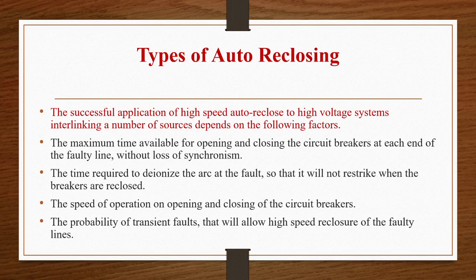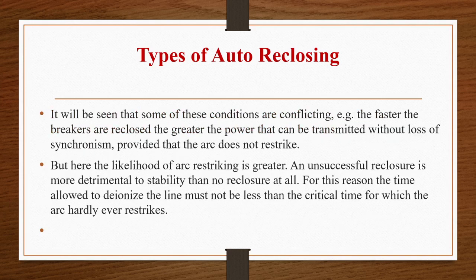Second one is the time required to deionize the arc at the fault so that it will not restrike when the breakers are reclosed. Third one is the speed of operation, or opening and closing, of the circuit breakers. Fourth one is the probability of transient faults that will allow high speed reclosure of the faulty line. So it will be seen that some of these conditions are conflicting. For example, the faster the breakers are closed, the greater is the power that can be transmitted without loss of synchronism, provided that the arc does not restrike.